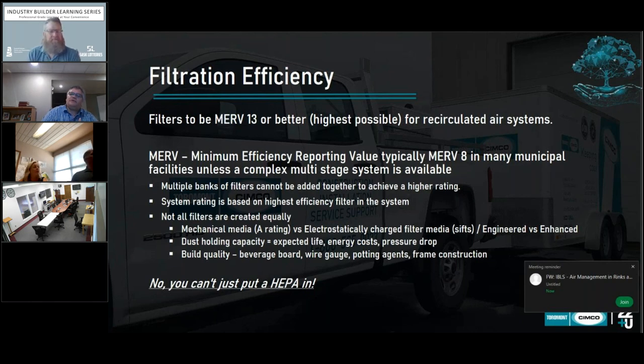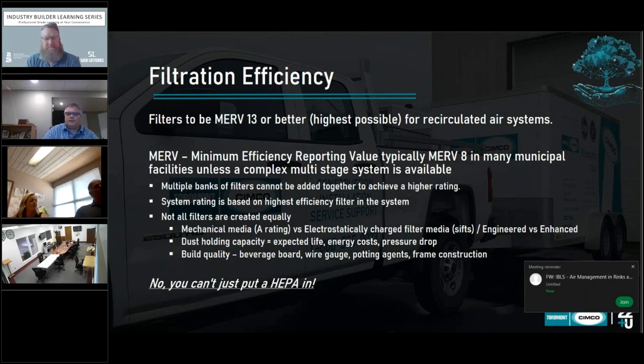For those of you with a slightly more complex system, which may be a multiplex or communiplex or a multi-use facility in a town, you can't go add two, three, or four banks of filters together and say this is eight, this is eight, this is eight, good, we've got 24, we're ready to go. The MERV rating is based on the most efficient filter in your system, not the cumulative effect of all your filters.